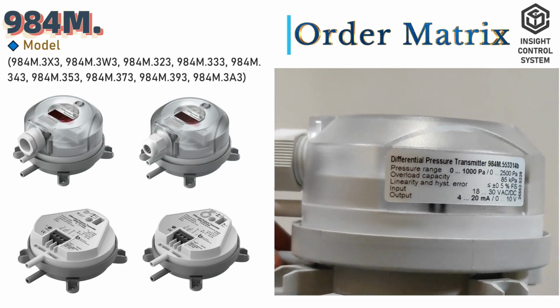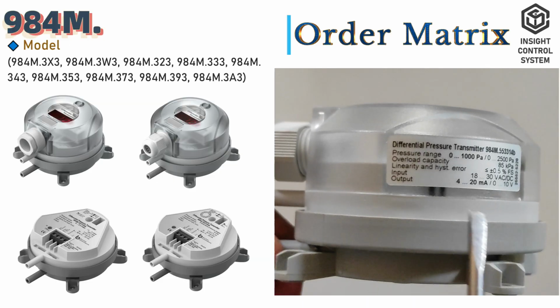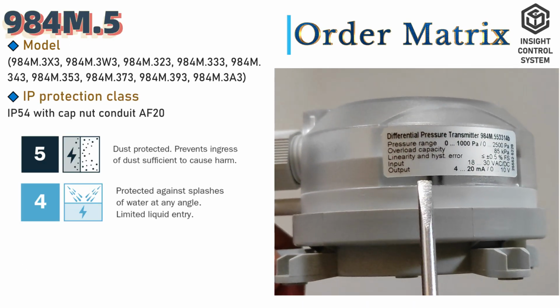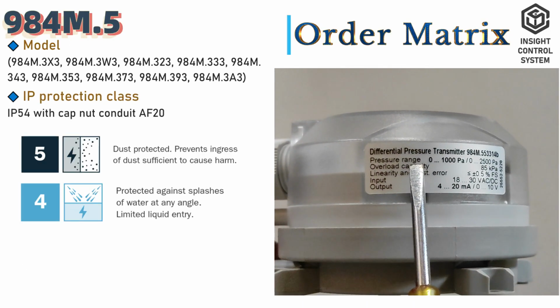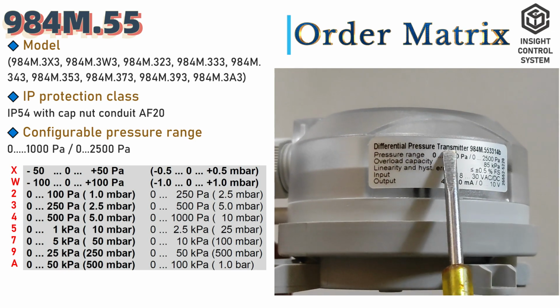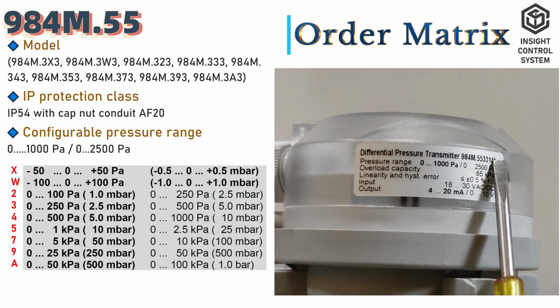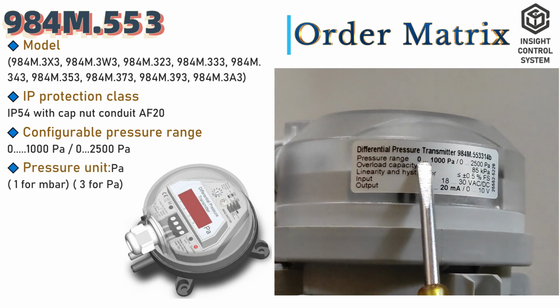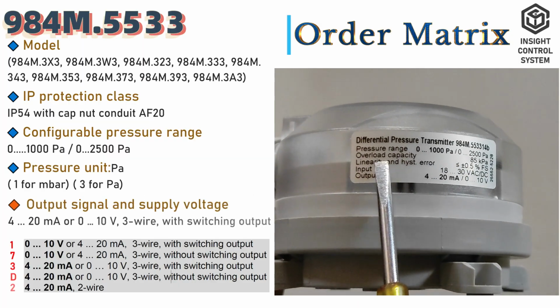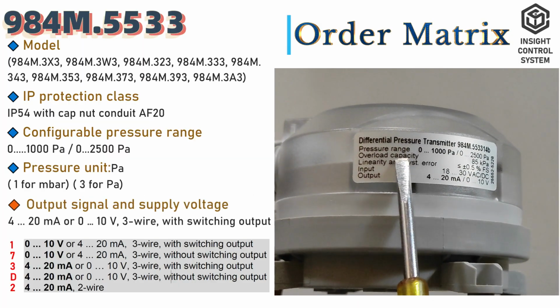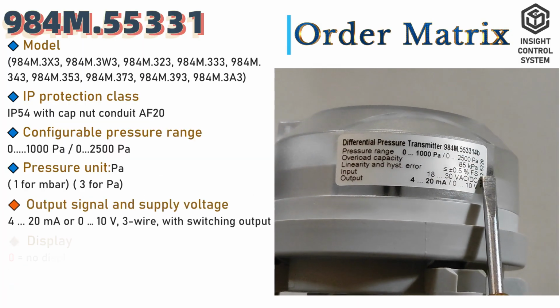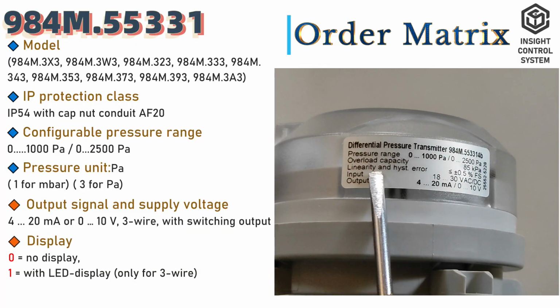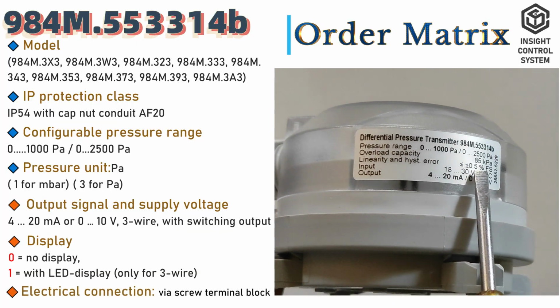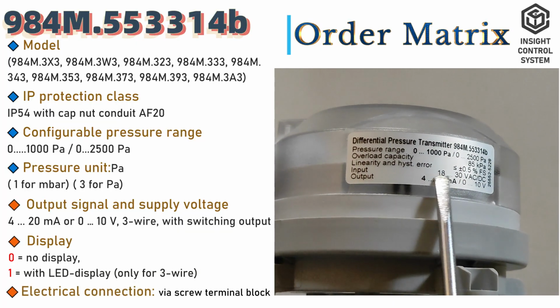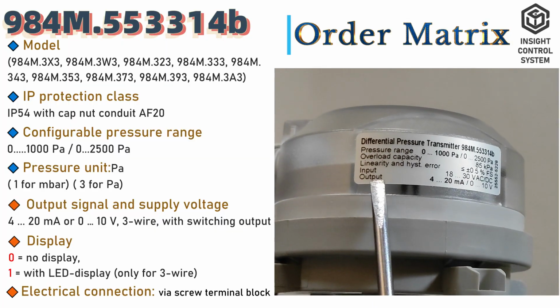The 984M indicates Beck DP sensor series. Next digit 5 indicates the IP protection class. Next digit 5 indicates the configurable pressure range. Next digit 3 indicates the pressure unit. Next digit 3 indicates the output signal and supply voltage. Next digit 1 indicates the display option. Next 4 and B indicates the electrical connection via screw terminal block option.